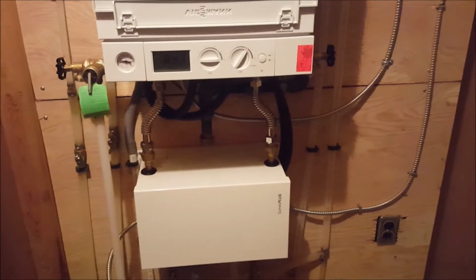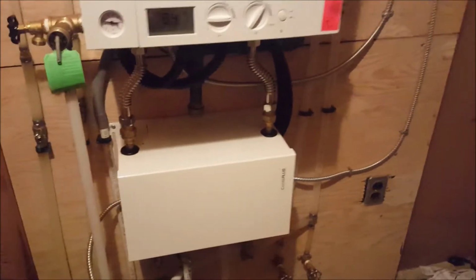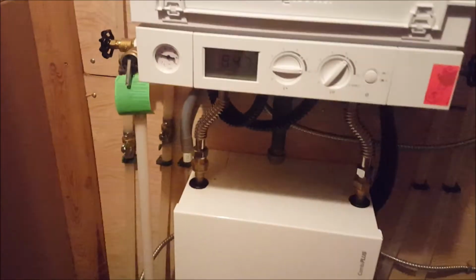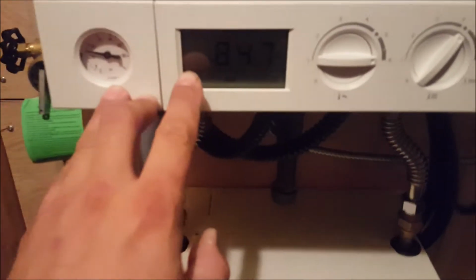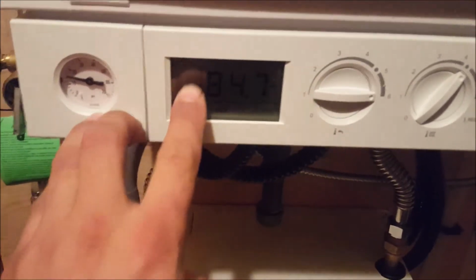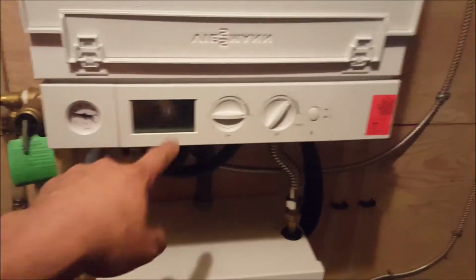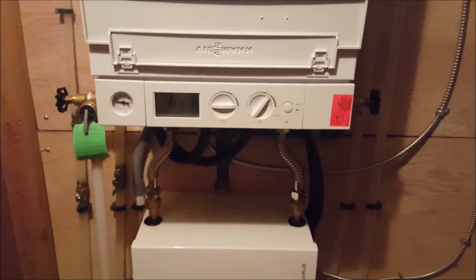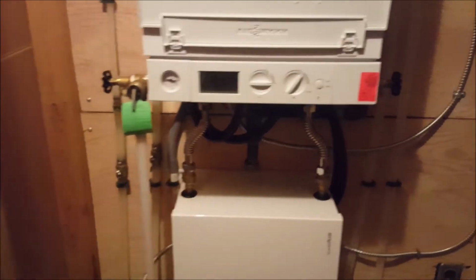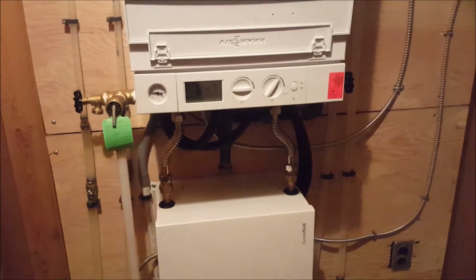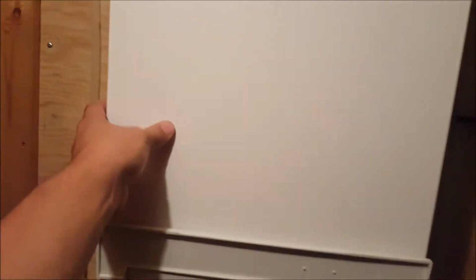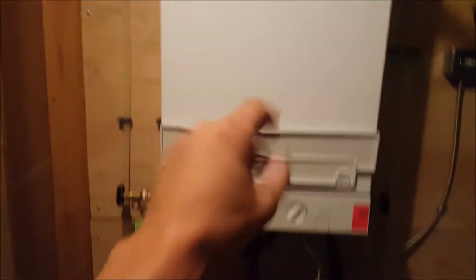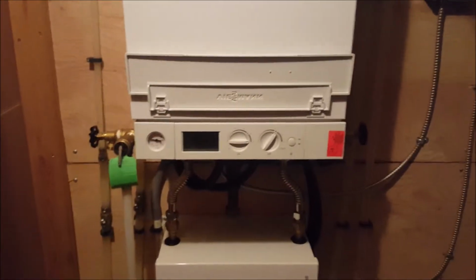Now, when you have a bad pump in this Combi Plus unit, it will display on your display either a tap or a rad symbol, showing it's trying to make hot water, but this will not fire up. And it's because with no circulation, it will not fire up and it will not throw an error code.